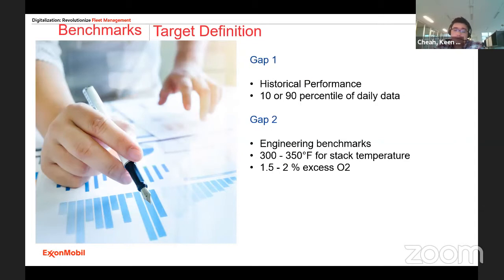Gap 2 benchmark is typically set by the best available technology. For example, stack temperatures of 300 to 350 degrees F using heat pipe air preheaters or glass-coated air preheaters, or 1.5 to 2% excess O2 that can be achieved with balanced draft heaters and proper heater burner maintenance programs.